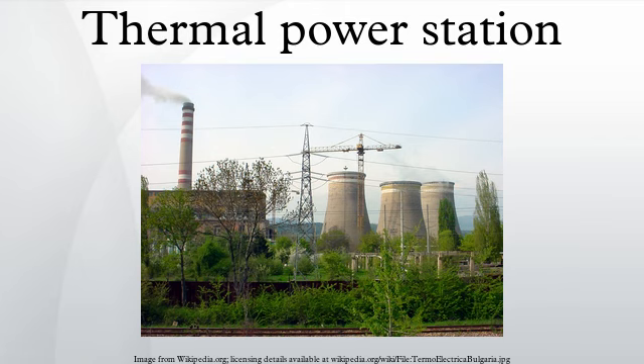Nevertheless, they may become internally fouled during operation by bacteria or algae in the cooling water or by mineral scaling, all of which inhibit heat transfer and reduce thermodynamic efficiency. Many plants include an automatic cleaning system that circulates sponge rubber balls through the tubes to scrub them clean without the need to take the system offline. The cooling water used to condense the steam in the condenser returns to its source without having been changed other than having been warmed. If the water returns to a local water body, it is tempered with cool raw water to prevent thermal shock when discharged into that body of water.